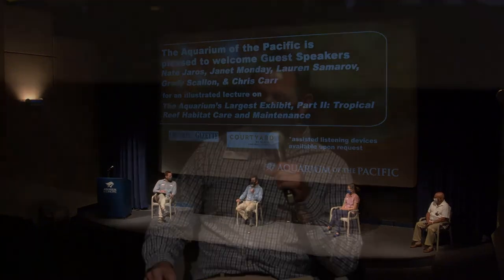Sure, I'd be happy to do that, Nate. Yeah, we get water from the seawater intake pump, and we are at the base of the Los Angeles River. So, of course, the water quality can be dynamic at times. So we make sure that we pump only at high tide. We don't pump 5 days after a rain because sometimes we're seeing contaminants in the water that we have trouble getting out. And then it's based on our ability to clean that water up to move it into our reservoirs. And we have to do that in batches.